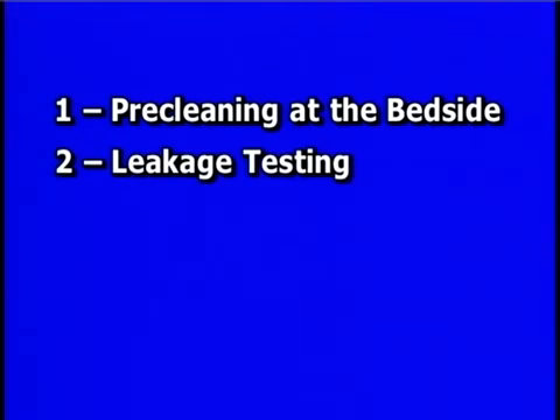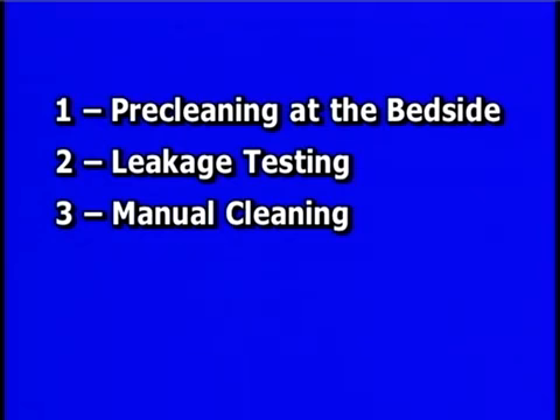2. Leakage testing is required to ensure that the channels and insertion tube are not damaged and that all seals are air and watertight. Routine leakage testing prevents costly fluid invasion and therefore costly instrument repairs. Never use an endoscope that has a known leak on a patient, as this can present an infection control risk. 3. A critical step is meticulous manual cleaning with a detergent or enzymatic solution. Use appropriate brushes and cloths to thoroughly clean all exterior surfaces and internal lumens.